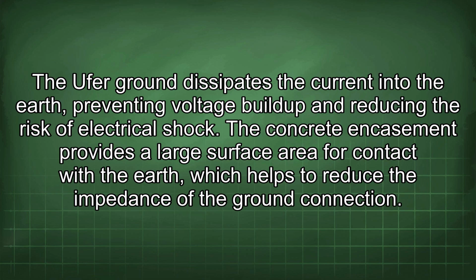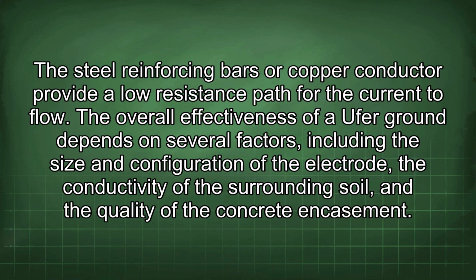The concrete encasement provides a large surface area for contact with the earth, which helps to reduce the impedance of the ground connection. The steel reinforcing bars or copper conductor provide a low resistance path for the current to flow. The overall effectiveness of a Ufer ground depends on several factors, including the size and configuration of the electrode, the conductivity of the surrounding soil, and the quality of the concrete encasement.